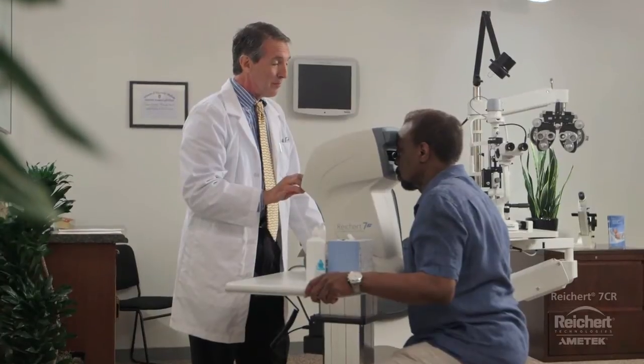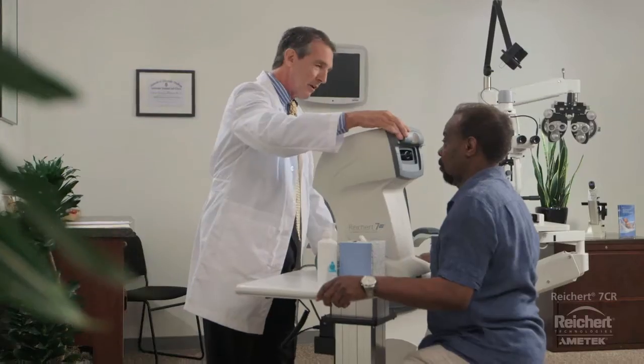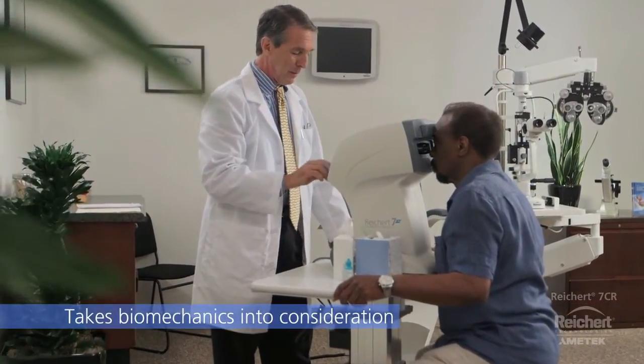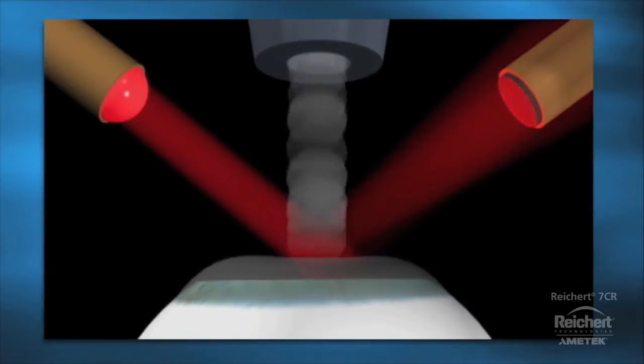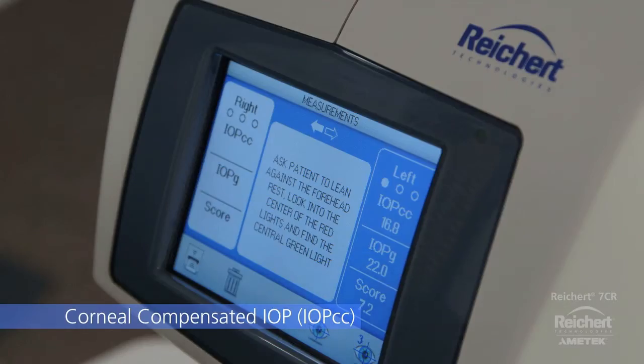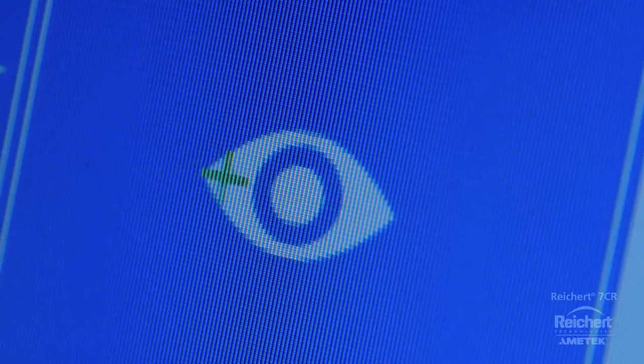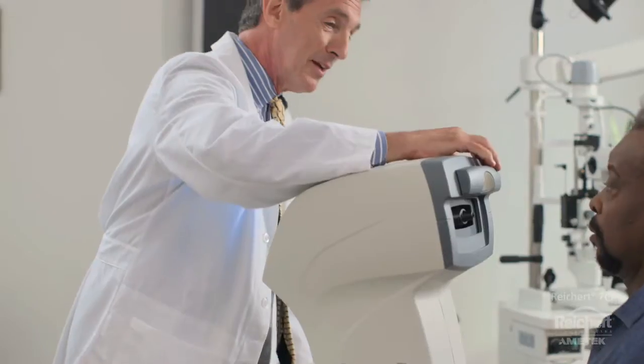Corneal biomechanics have the most significant influence on the accuracy of IOP measurements. Reichert 7CR utilizes a unique patented corneal response technology that takes biomechanical properties into consideration in determining the IOP. Using a rapid air impulse, the Reichert 7CR monitors the inward and outward movement of the cornea. This dynamic bidirectional applanation process enables determination of corneal viscoelastic properties. The resulting measurement, called corneal compensated IOP or IOPCC, has been shown to be more associated with glaucoma risk and progression than Goldman or other tonometers. It is virtually unaffected by corneal thickness, corneal pathology, or surgical procedures such as LASIK.